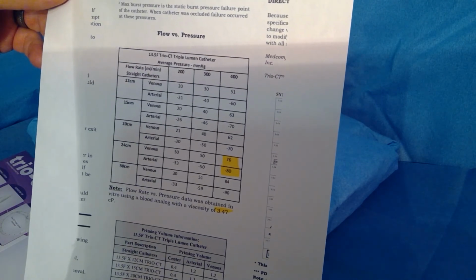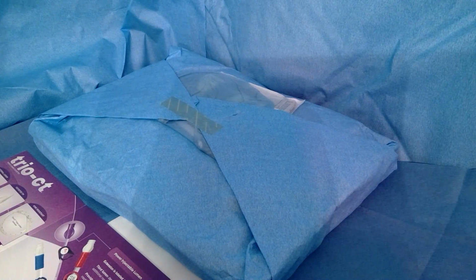So 76, -80. If you take the IFU out of your Bard Dialysis catheter and look at that, it's pretty interesting because at 400 flows on a 24 centimeter catheter, now granted this has curved extensions, so that counts for a little bit of the difference, but the venous pressures are 197 and the arterial are -204. That's pretty significant. So this catheter clearly outperforms anything that's out there right now that's power injectable.